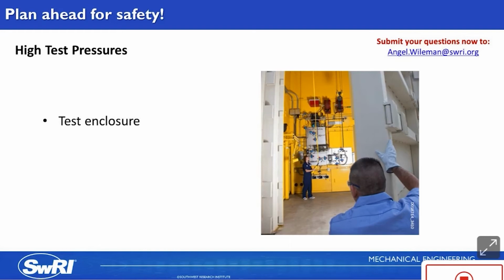The test cell design required a very thorough analysis, including computational fluid dynamics and prediction of projectile motion to predict the blast loads due to sudden valve failure that would cause a blind flange or another piece of tubing to become a projectile. The walls of the cell contain a 1-inch thick steel plate and horizontal stiffeners, and they were designed to absorb the impacts of an 11-pound bull plug pressurized to 30,000 psi with nitrogen gas.